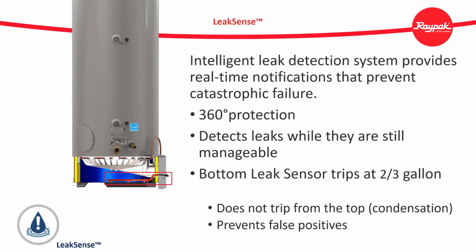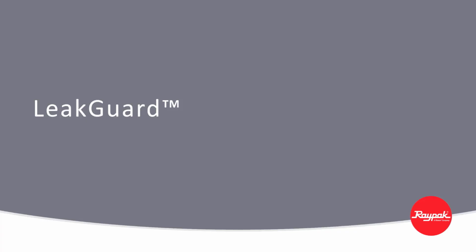The feet lift the leak sense tool slightly above the bottom of the pan. This is by design to avoid false positives from washdowns or condensation drips. We want a little accumulation in the pan to validate the leak. We determined that 2.5 liters is a good place to be for avoiding false positives but still detecting the leak. All of the water will be caught inside of this pan. 2 of the feet have magnets to keep the leak sense tool affixed to the bottom. The leak guard system is standard in the SS models.